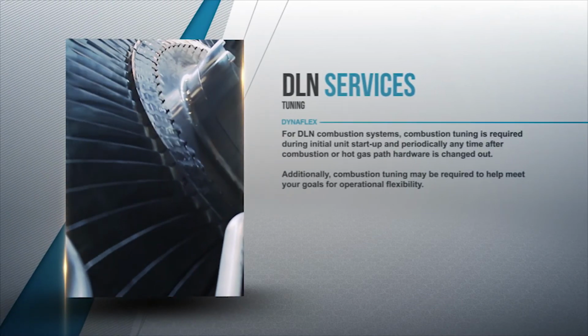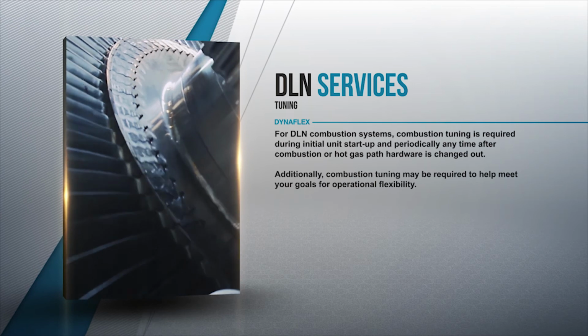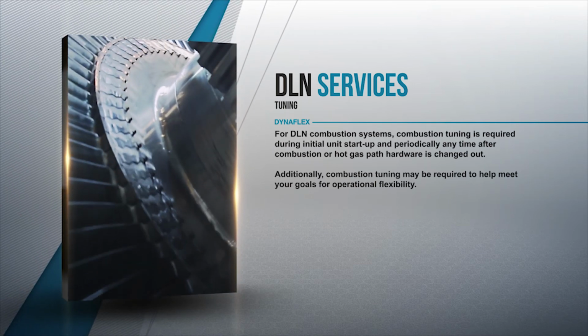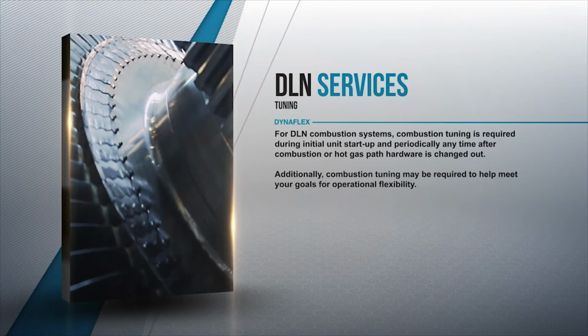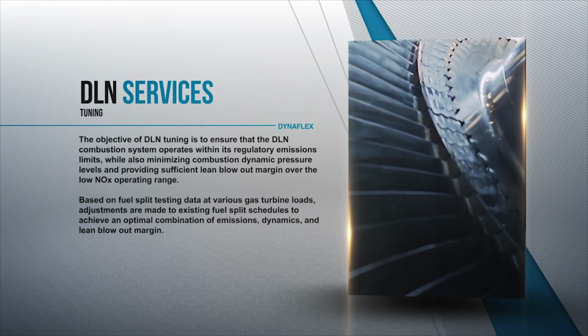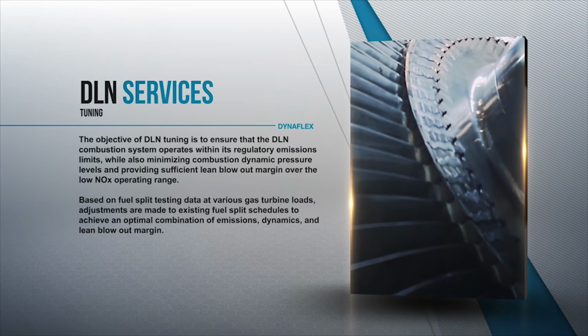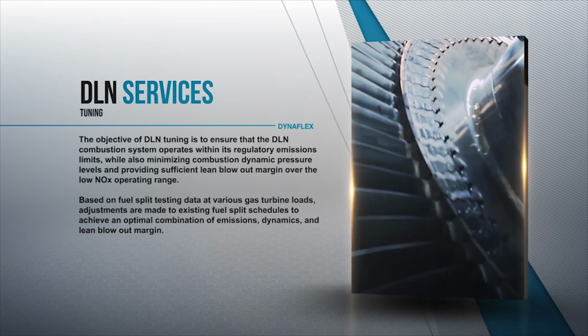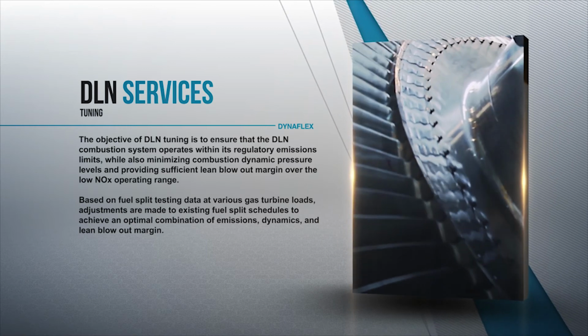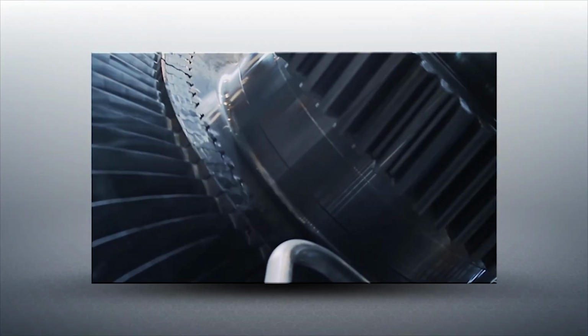Combustion tuning is required for DLN combustion systems during initial unit startup and periodically any time after combustion or hot gas path hardware is changed. DLN tuning ensures that the DLN combustion system operates within its regulatory emissions limits, while minimizing combustion dynamic pressure levels and providing sufficient lean blowout margin over the low NOx operating range.